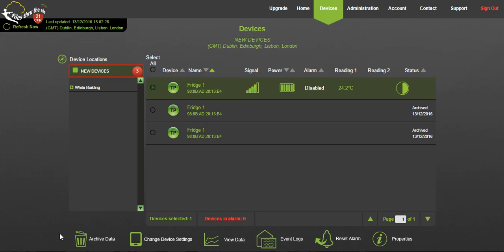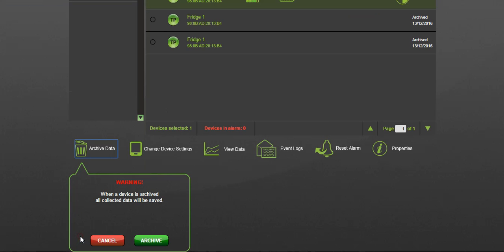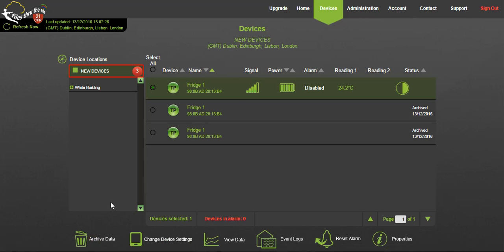Firstly, if you wish at any stage to stop a logger and archive its data, you can do so by clicking the archive data button. A warning will appear before data is archived and when clicking the archive button an approval window will also appear. Enter your account details to continue. This approval is part of 21 CFR compliance, creating a record of any change made to the system or device for audit purposes.